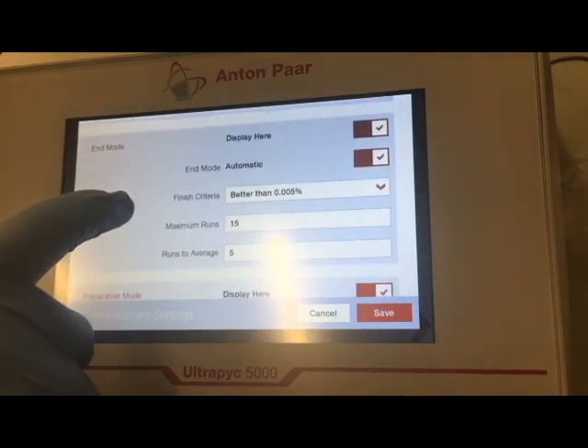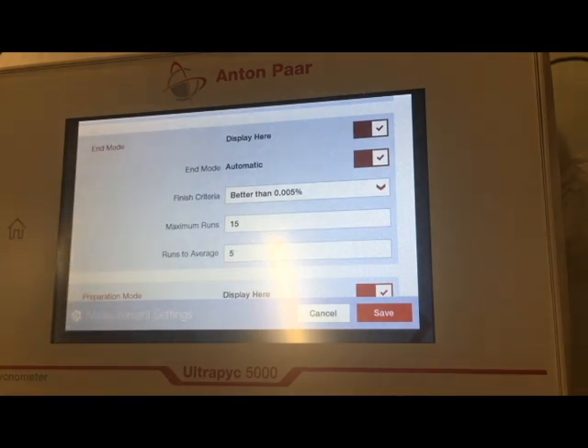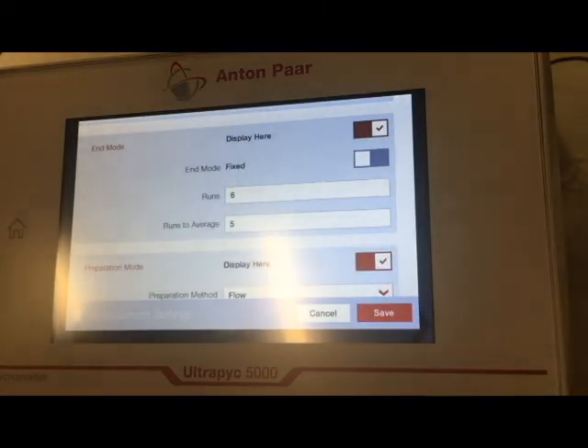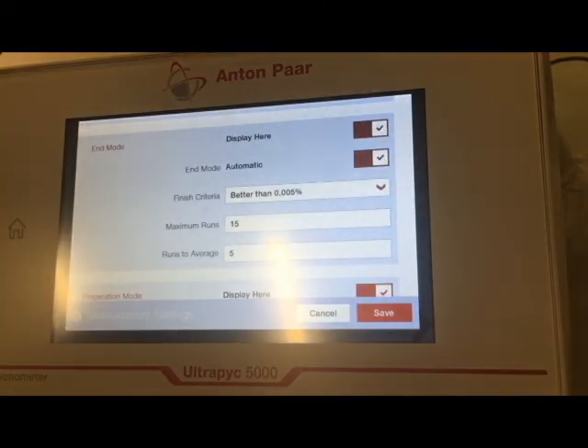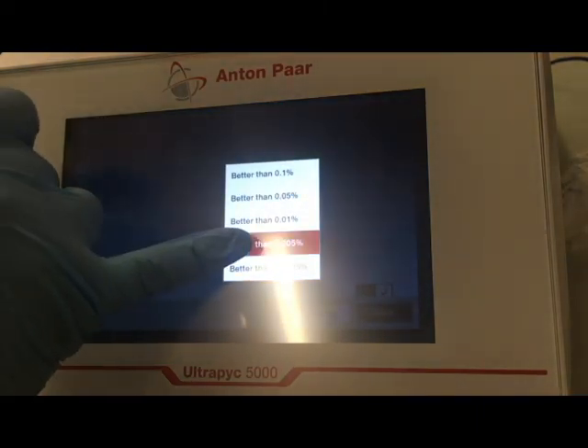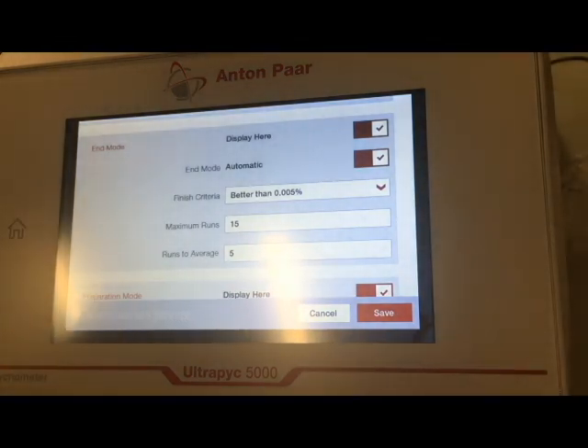And now we're going to go through each of these settings. End mode, just like was done in the calibration section, this can be either automatic or fixed. Automatic is what is recommended. That's going to give you a very low percentage of error in the set of your runs. We have a range of less precise to more precise. 0.005% is the typical recommended. We're going to set a maximum number of runs so that it does not keep running forever in case it's having a very difficult time in narrowing down that error margin. And then we're going to select runs to average.